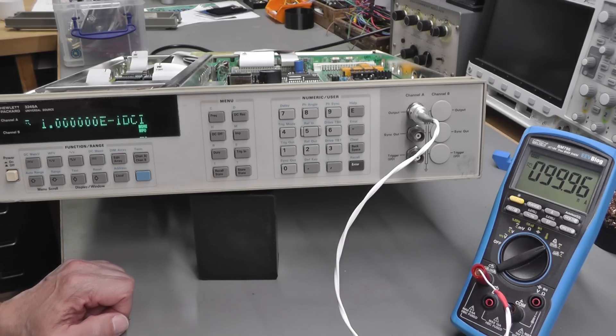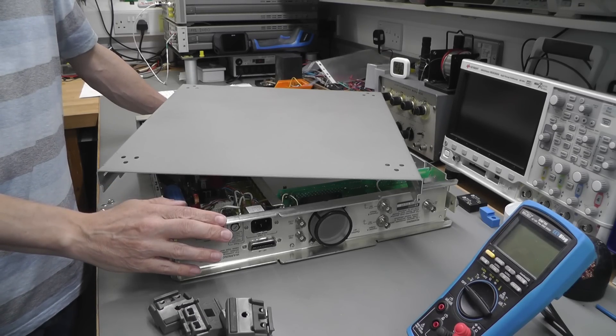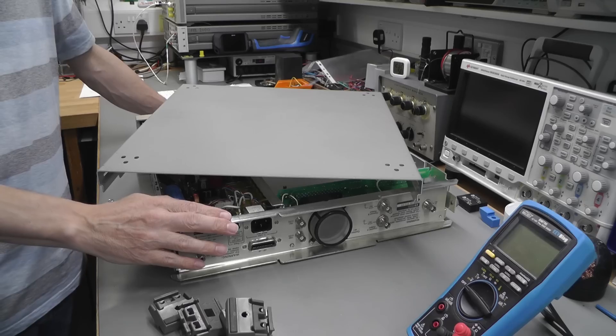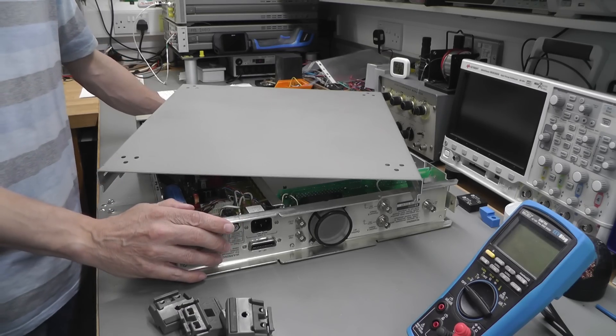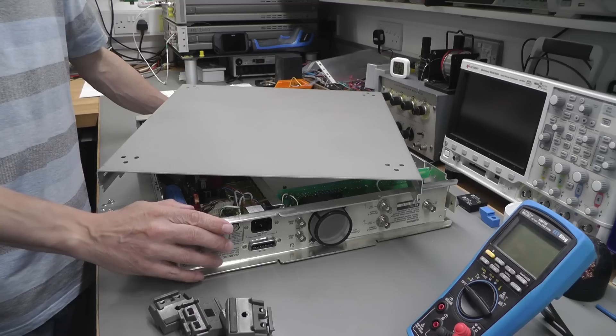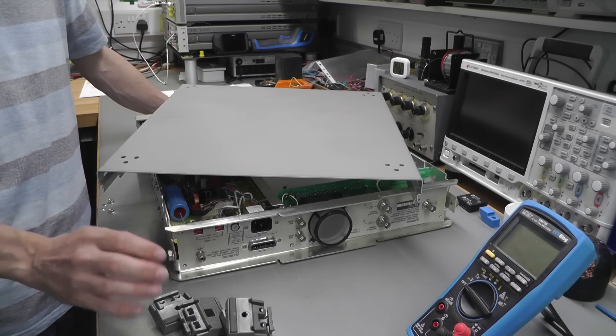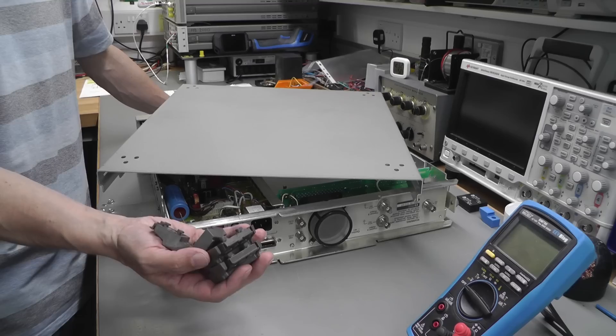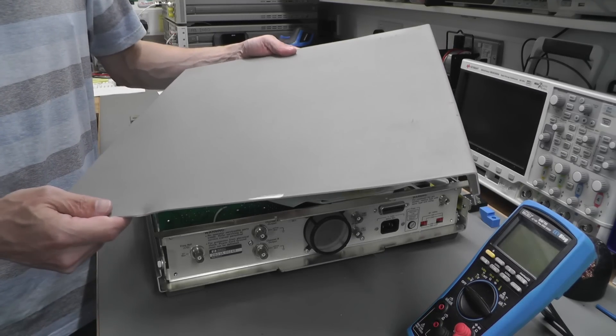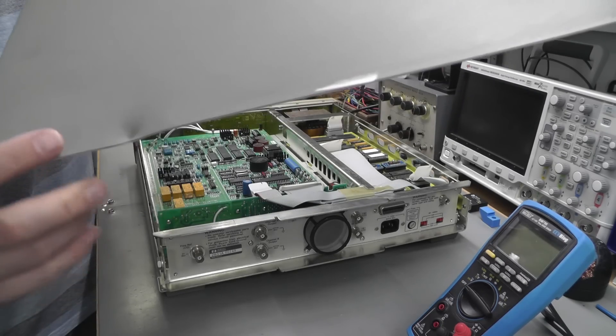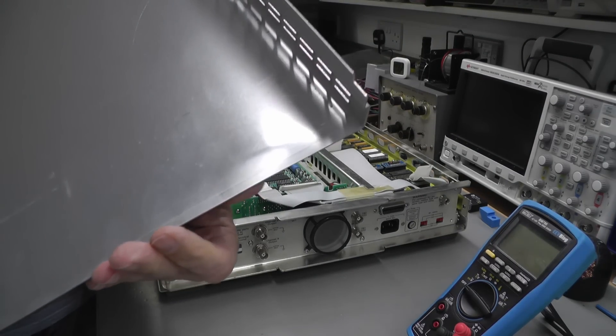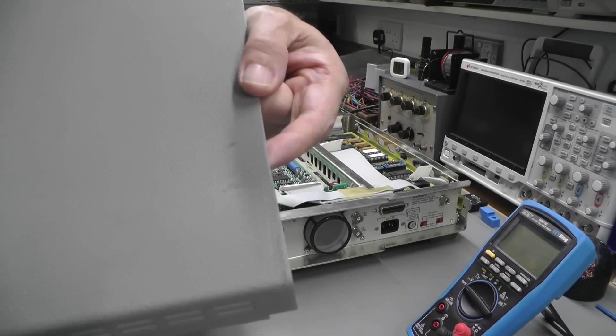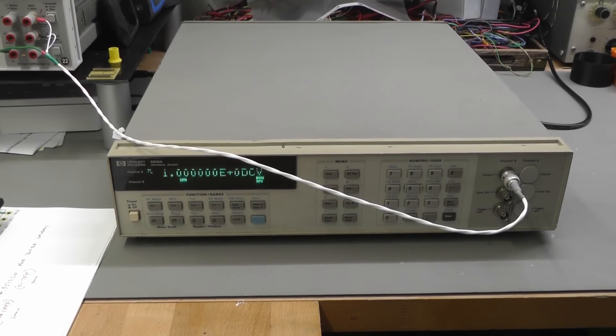Okay, so the next step is actually to recap all the boards inside the 3245A, but I'm actually going to run some tests in advance of that whilst I'm waiting for the capacitors to arrive. I want to power the unit up and run some stability tests, so I need to pop the covers on. And I do actually have a set of HP feet here that I've had in storage for quite a while, so I'm going to fit them before I put the covers on. Now of course, as I showed earlier, the top of this unit does actually have some quite heavy dings on it, so I'm going to have to hammer them out before I fit it, but I'll do that off-camera. And here's the 3245A powered up. I've got it set to 1-volt output and I've got it hooked up to my 3458A which you can see over there, and it's reading quite low actually, so this unit is in dire need of calibration. So I'm actually going to go ahead and do that now.